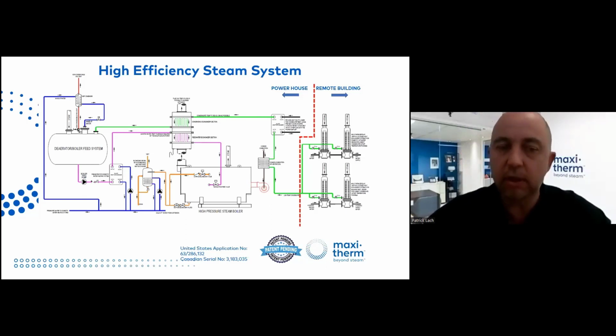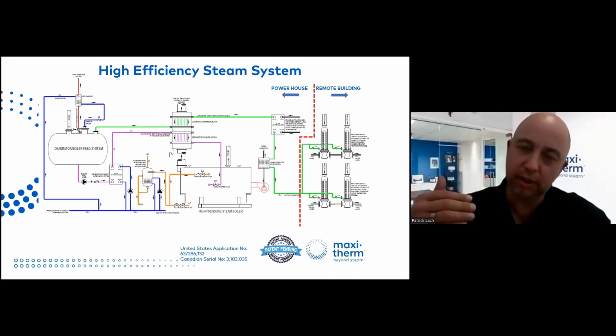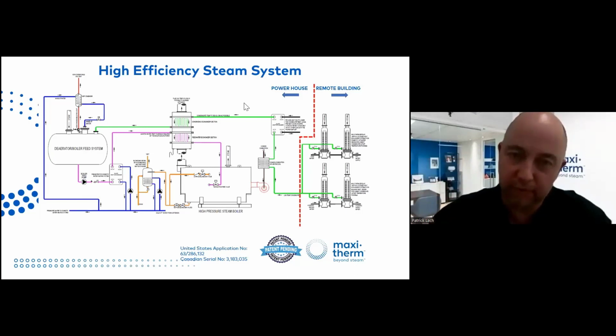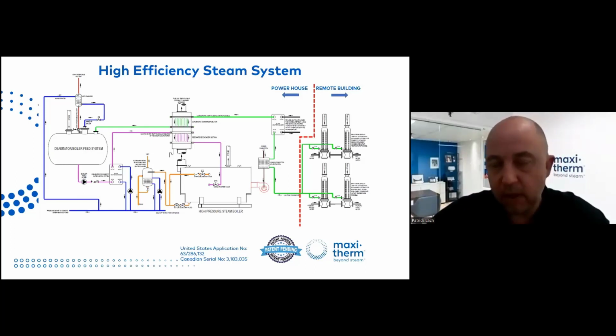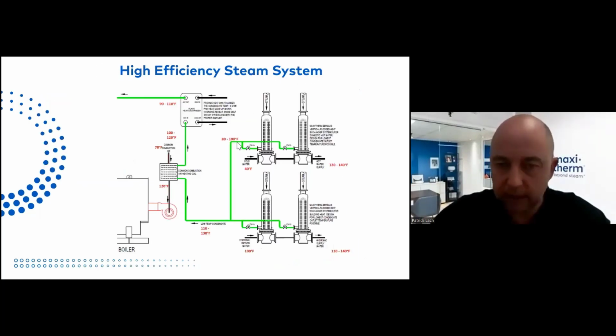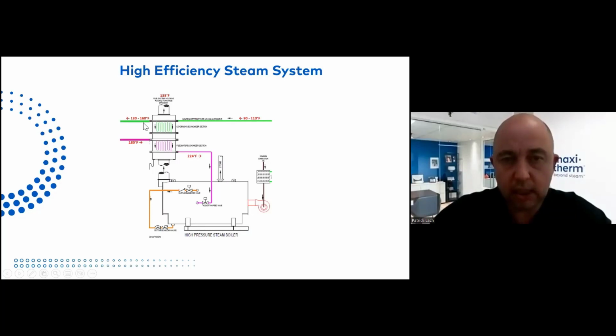So we want to get condensate as cold as possible before getting into the condensing stack economizer stage right here, to get as much benefit as possible. So that's the basic concept of the 100% steam condensate closed loop. All right, so like I said, we're coming back here, let's say 110, 120-ish, coming back as cold as possible to the condensing stack economizer stage, and then going back into the main receiver tank.